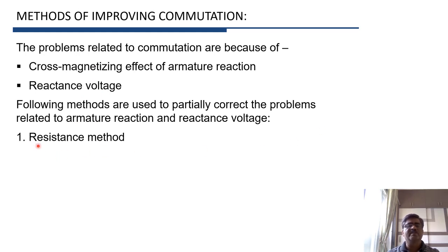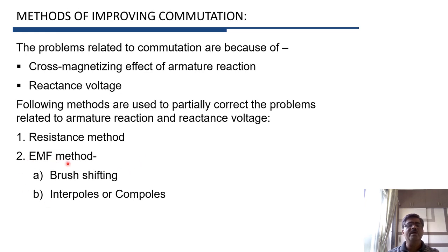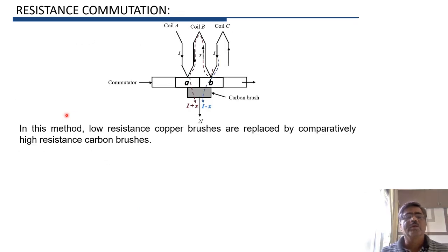The first method is called the resistance method. In this method we use carbon brushes instead of low-resistance copper brushes to reduce sparking at the brushes. The second method is called the EMF method, in which we induce an EMF equal and opposite to the reactance voltage in the coil, thereby obtaining sparkless commutation. We will study the resistance method in this video and the EMF method in our next video. Let us now see resistance commutation — in this method the low-resistance copper brush is replaced by a high-resistance carbon brush.